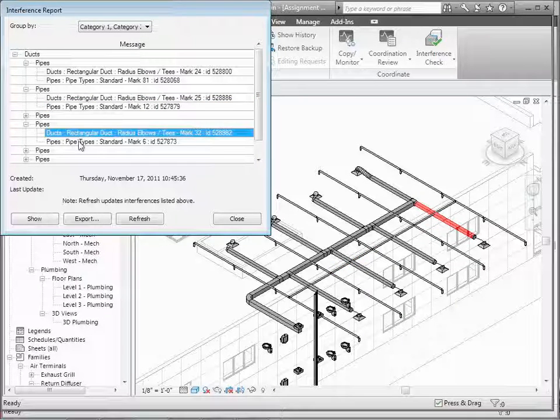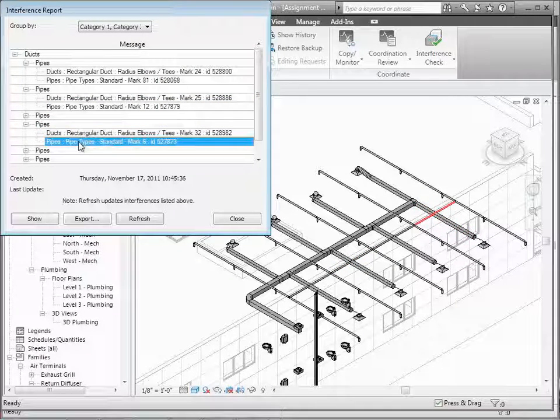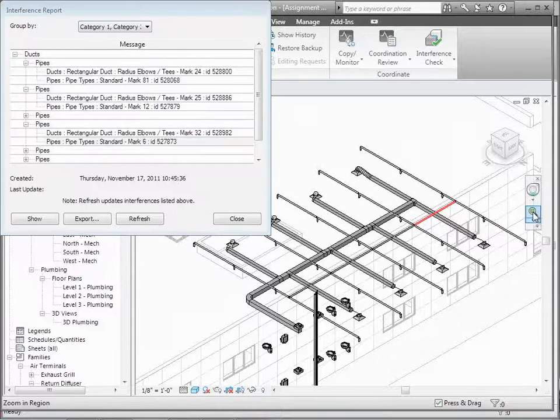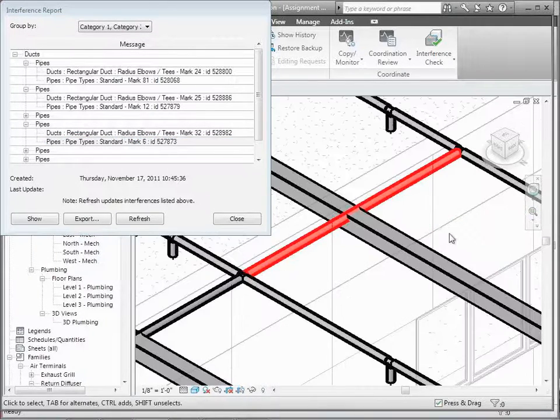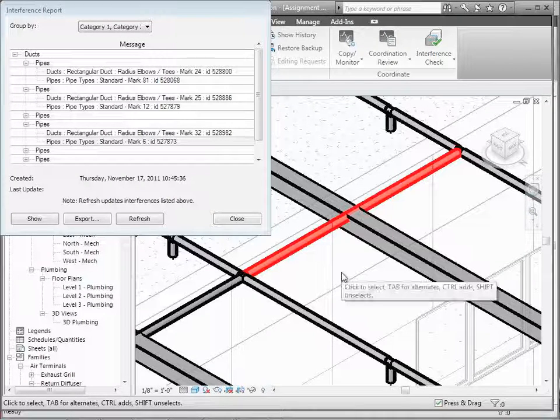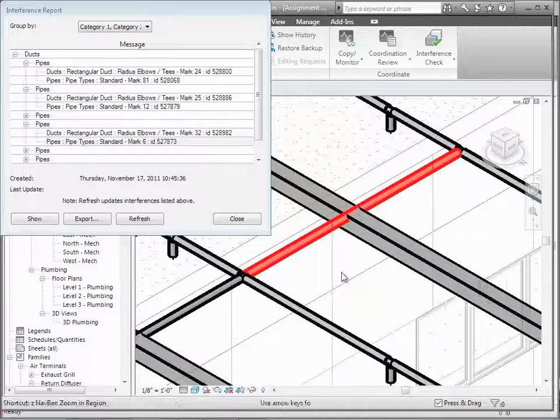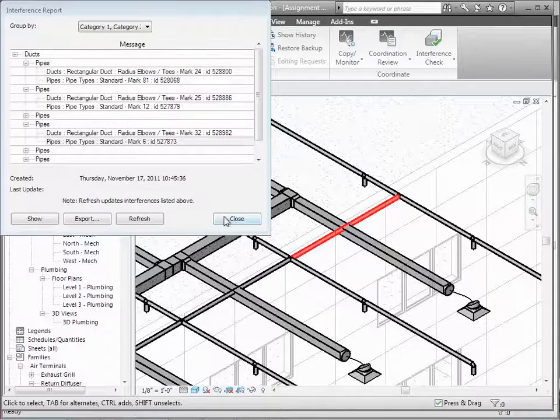Looking at these one by one, you're going to start getting the sense that there's a problem with my sprinkler system and my ductwork — everything's running at the same level. So we need to do something about that. We can fix that right here in Revit. If I zoom in to see where it's all happening, I'll close the report for now and take a look at that pipe to see if we can do anything with it.